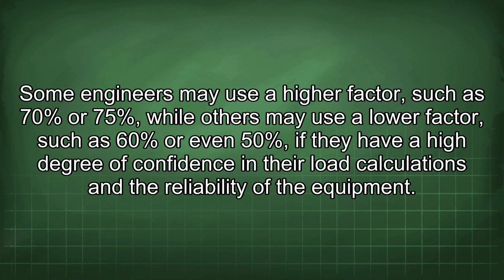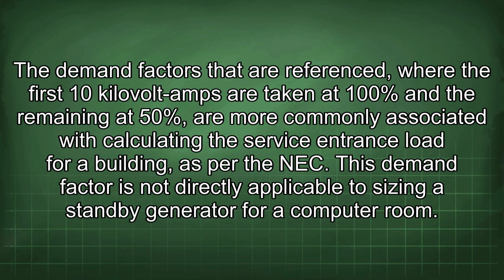Some engineers may use a higher factor, such as 70% or 75%, while others may use a lower factor, such as 60% or even 50%, if they have a high degree of confidence in their load calculations and the reliability of the equipment. The demand factors that are referenced, where the first 10 kVA are taken at 100% and the remaining at 50%, are more commonly associated with calculating the service entrance load for a building, as per the NEC. This demand factor is not directly applicable to sizing a standby generator for a computer room.